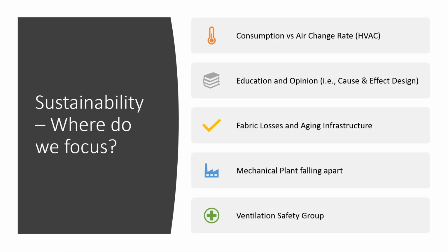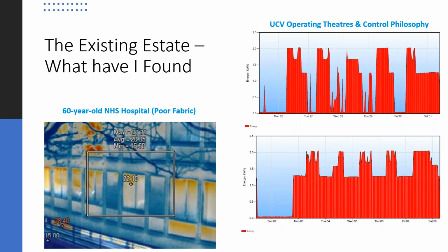So to summarise then, part A in sustainability: consumption versus air change rate, we need to look at the patient against the air change rate. Education and opinion: we need to look at cause and effect and how we tie these things in. Fabric losses and ageing infrastructure: mechanical plant is falling apart, and some of the plant we see really needs to be looked at and worked out. And then the ventilation safety group is another key part of that document. So the existing estate then, and what I found, this formed part of my dissertation.